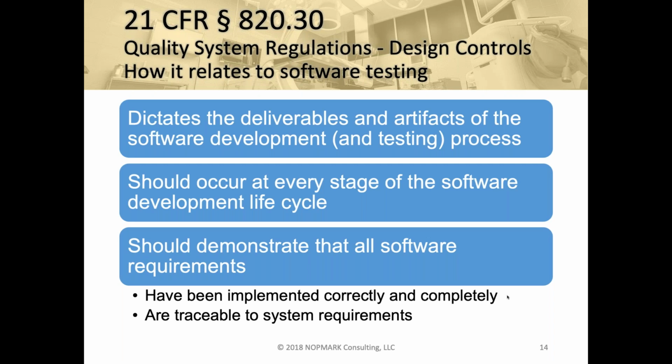The traceability between requirements and test cases. So this is the other deliverable that a software tester has to provide in the medical device world. It's not just the test cases and the test plans, but that traceability, and often this is done in a traceability matrix, to show that, yes, there is full coverage of everything.